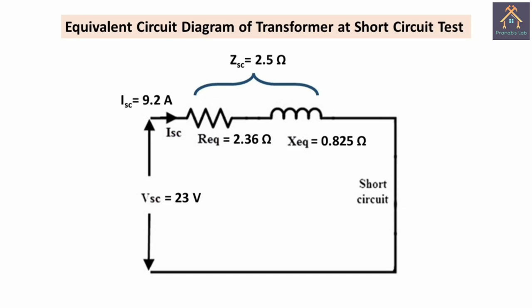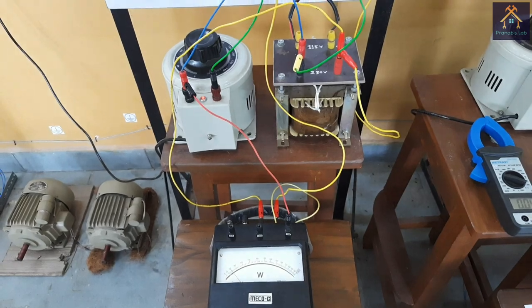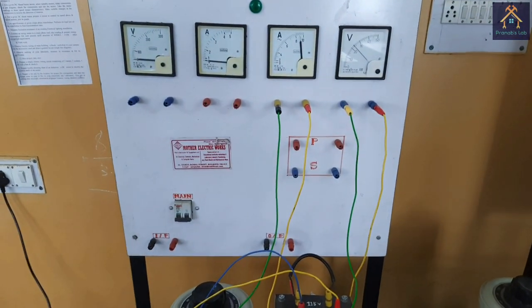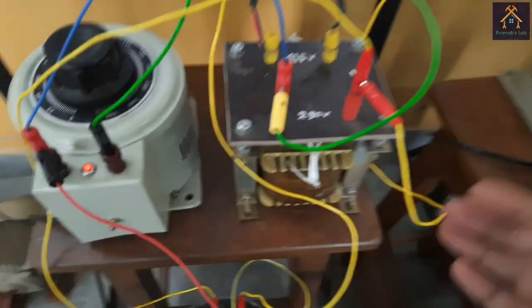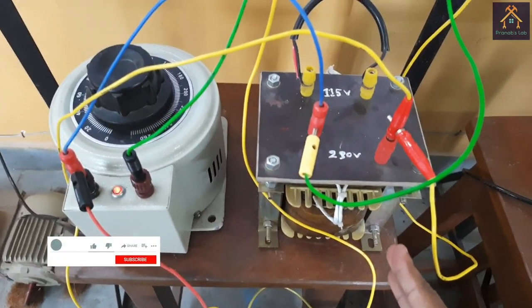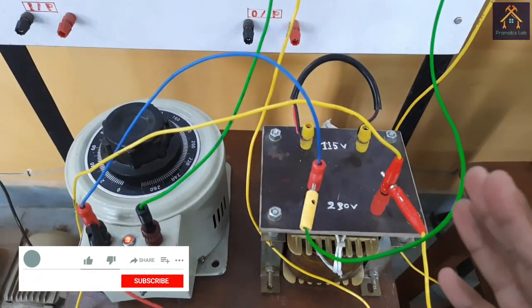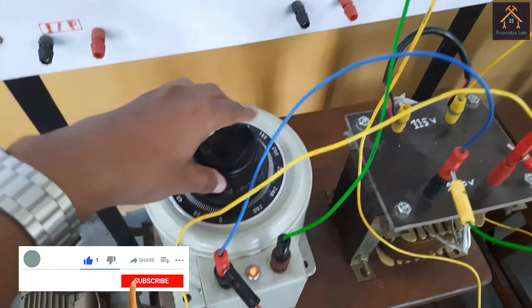This is the equivalent circuit diagram of the transformer at the short circuit test. This circuit contains only the total equivalent resistance referred to primary, the total equivalent reactance referred to primary, and the combination of these two is the short circuit impedance. This experiment is now performed, and the transformer is very hot, so we have to handle it with care. Now let's reduce the voltage and switch off the supply.